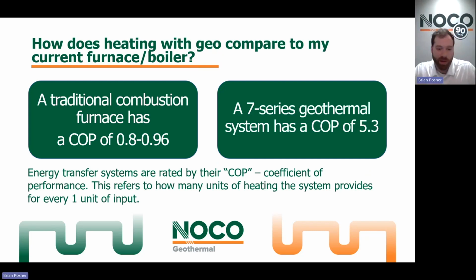So coefficient of performance, what does that mean? It means, of how much of the fuel source you're putting through a system, how much heat you're actually getting out of it. So electricity, natural gas, propane, they all have latent thermal content that, by combusting or running through electric resistance, you can get that thermal content to come out and be expressed as heat. Now, the COP, the coefficient of performance, shows the percentage of that potential energy that's actually converted into heat energy.